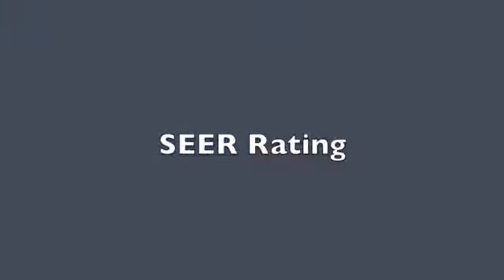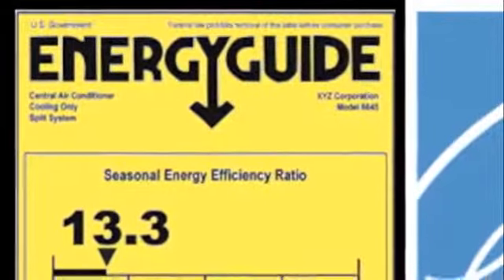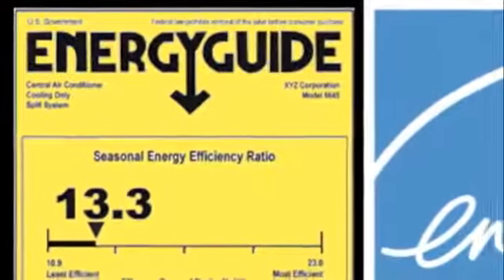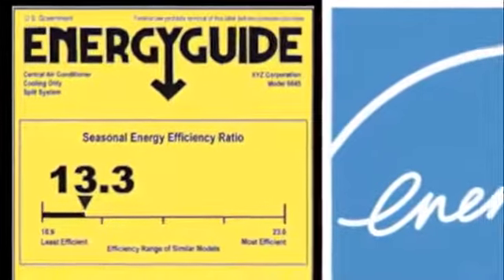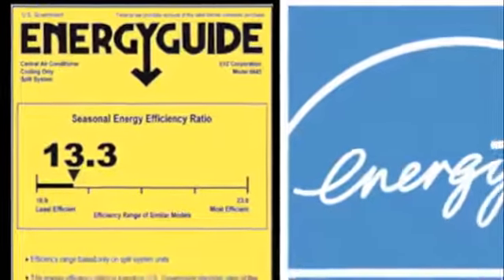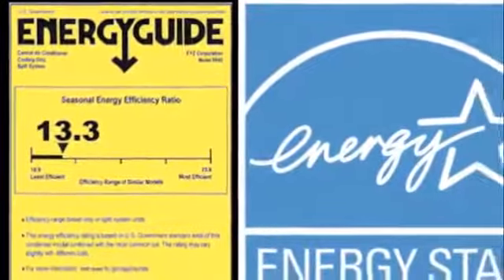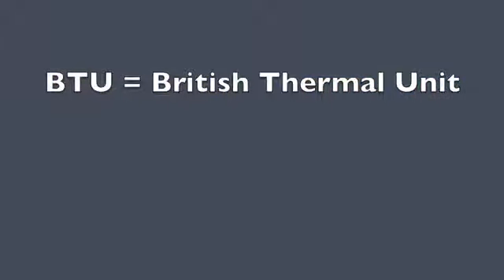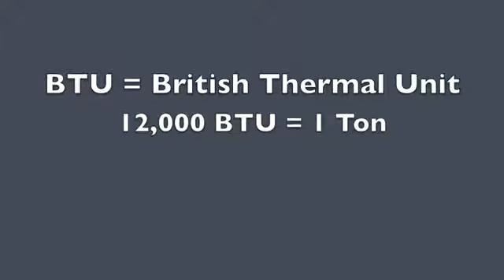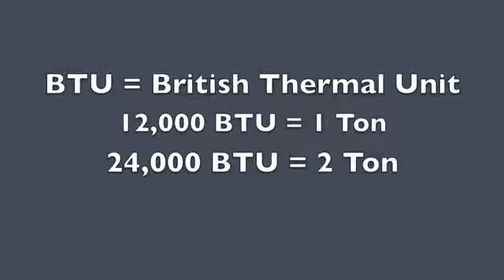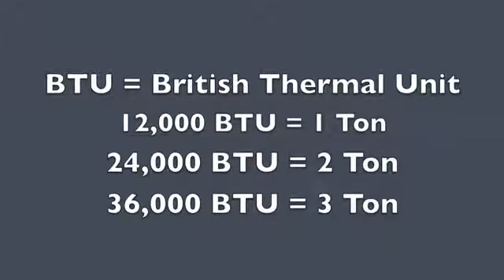Let's touch on the SEER rating. SEER stands for the Seasonal Energy Efficiency Ratio. The SEER ratings are how efficient a unit is at converting wattage into cooling power, or BTUs. It's calculated by taking the BTUs divided by the energy usage in watt hours. Now a quick note, BTUs stand for British Thermal Units. And if you've ever heard of a 1 ton, 2 ton, etc. in cooling power, 12,000 BTUs is essentially equal to 1 ton of cooling power, and 24,000 BTUs, 2 tons, and so on and so forth.